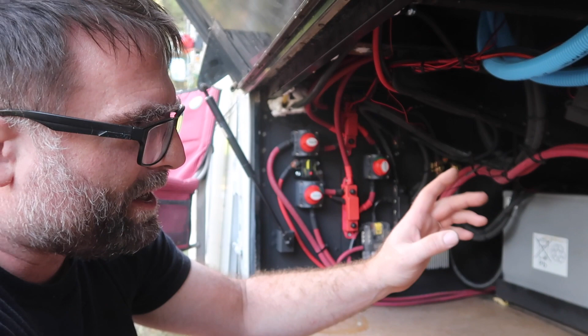They can go discharge deeply. So you have a 2x6, two in series, 6 in parallel battery array. We move these cables to the far end. You'll see that they're double cables, and what they do is they connect into these 2 disconnects, and then they go to these 2 bus bars, and then there's a bus bar interconnect. This gives you the ability to balance the current draw and return from both charging and discharging on this circuit.